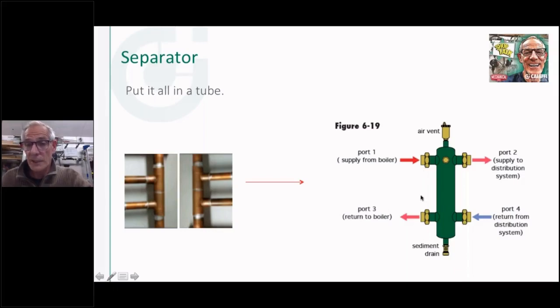And if you look at it, there's my closely spaced T, so I could have my boiler connected over here with its required circulator on it, circulating through there. And then over here on the distribution side, I could have a circulator, I could have multiple circulators, I could have a circulator with zone valves, I could have different size circulators. And this little chamber, I say little, I'll show you the size of that in a minute. This chamber in the center is what establishes that disconnect, that hydraulic separation that we're getting between these closely spaced T's and this common pipe here.